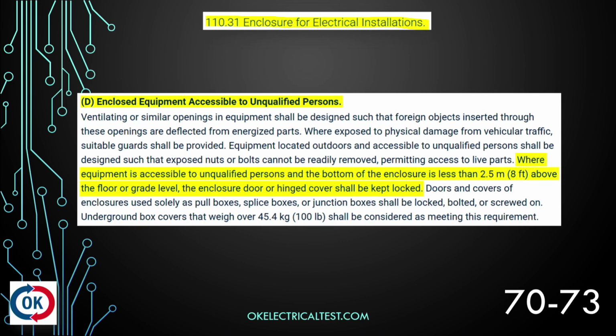Letter D, enclosed equipment accessible to unqualified persons. We're going to skip down a few lines in there. It says where equipment is accessible to unqualified persons and the bottom of the enclosure is less than 8 feet above the floor or grade level, the enclosure door or hinged cover shall be kept locked. So if I'm not elevating that up above 8 feet, right? We need to have that back behind some sort of locked cabinet or enclosure.